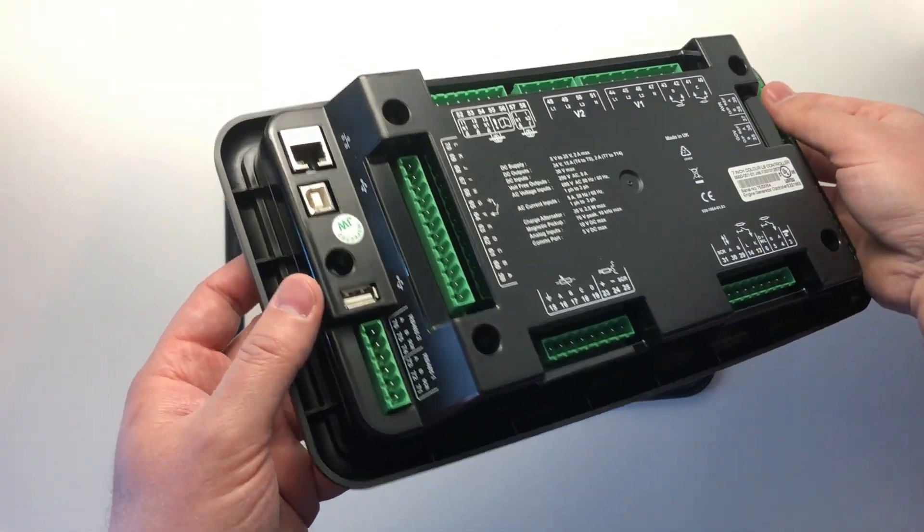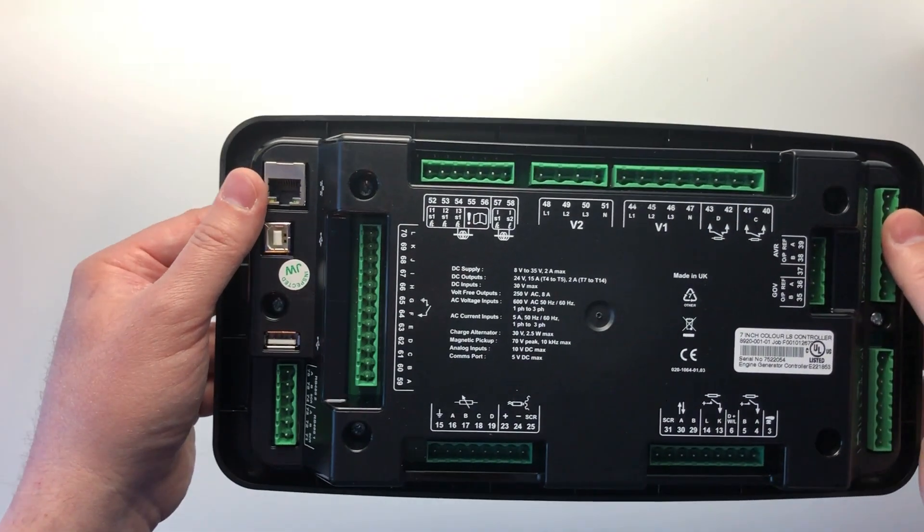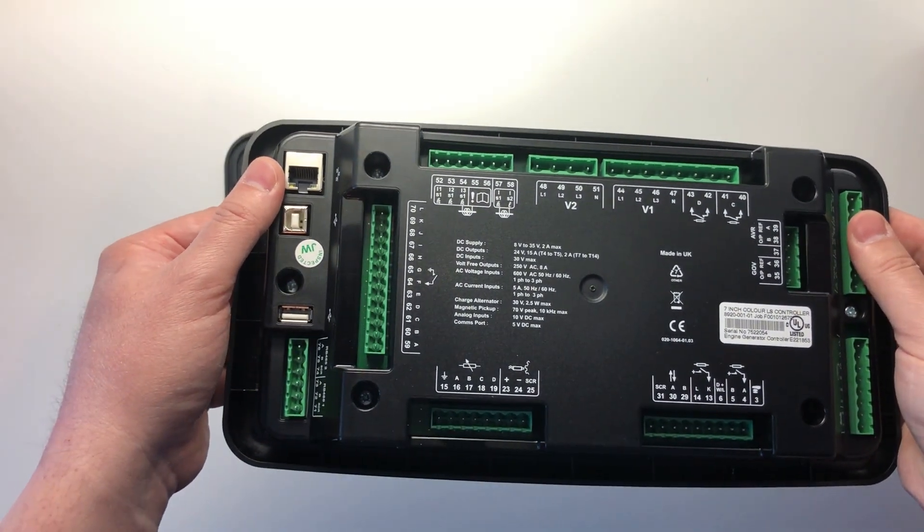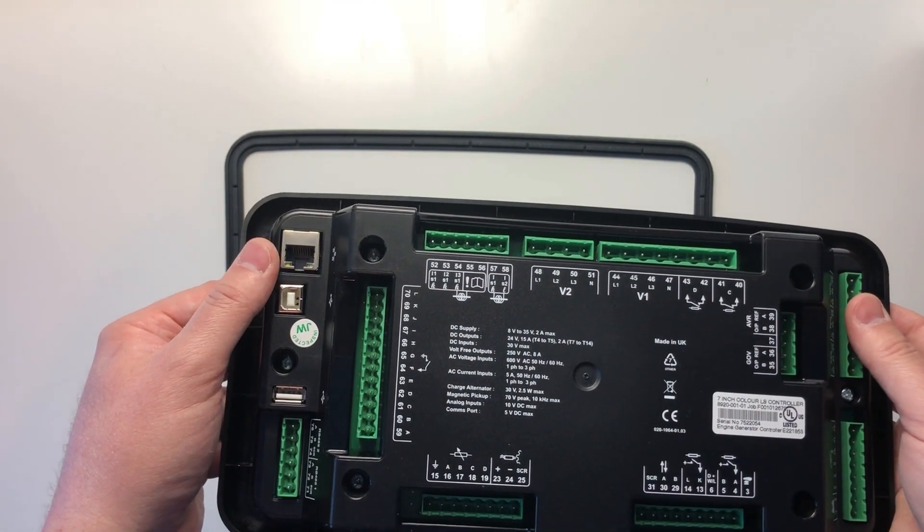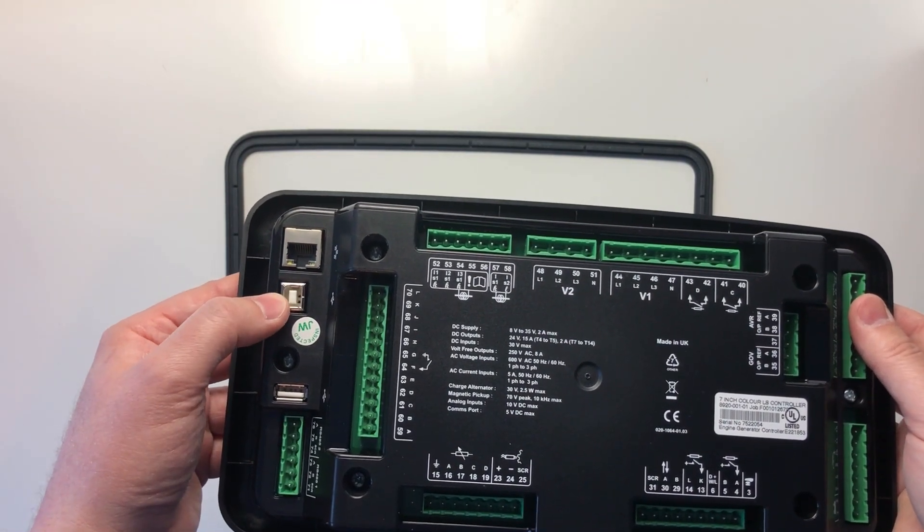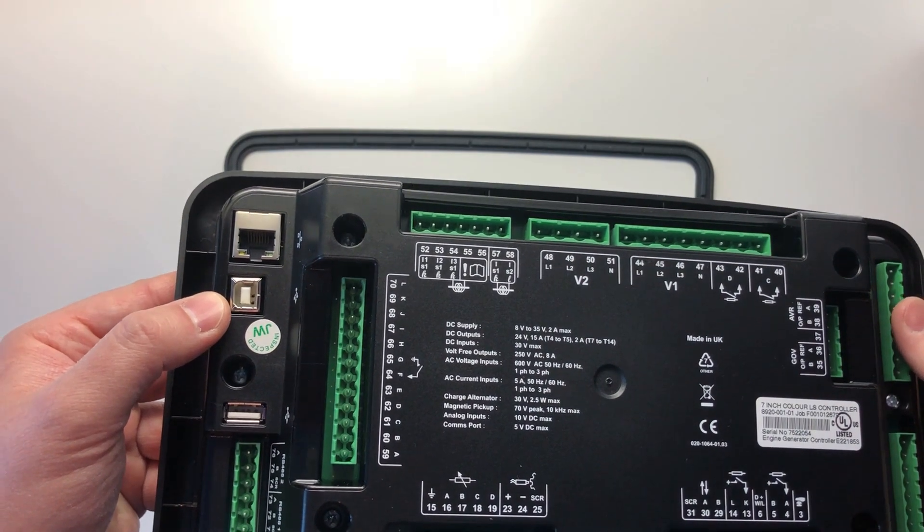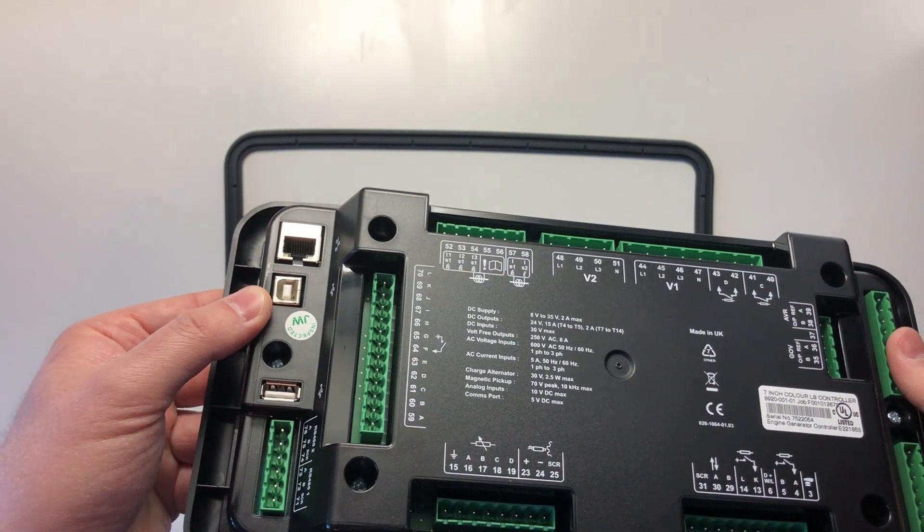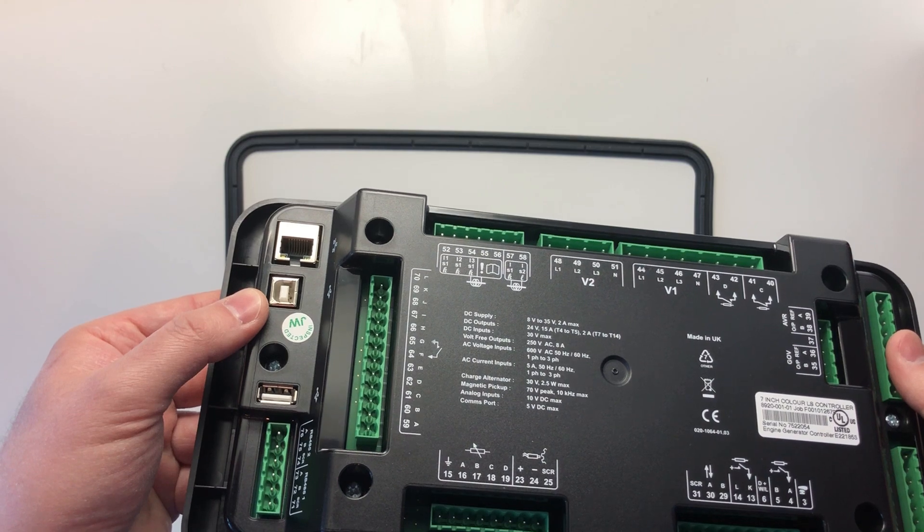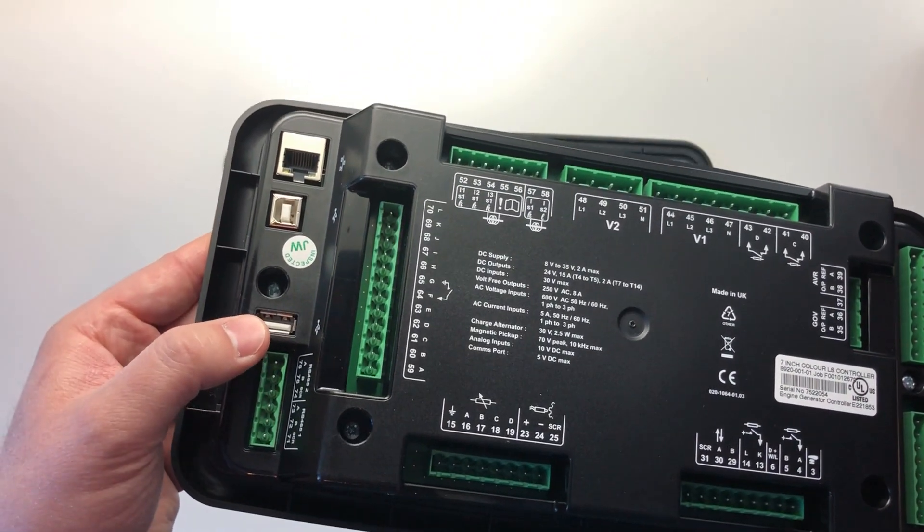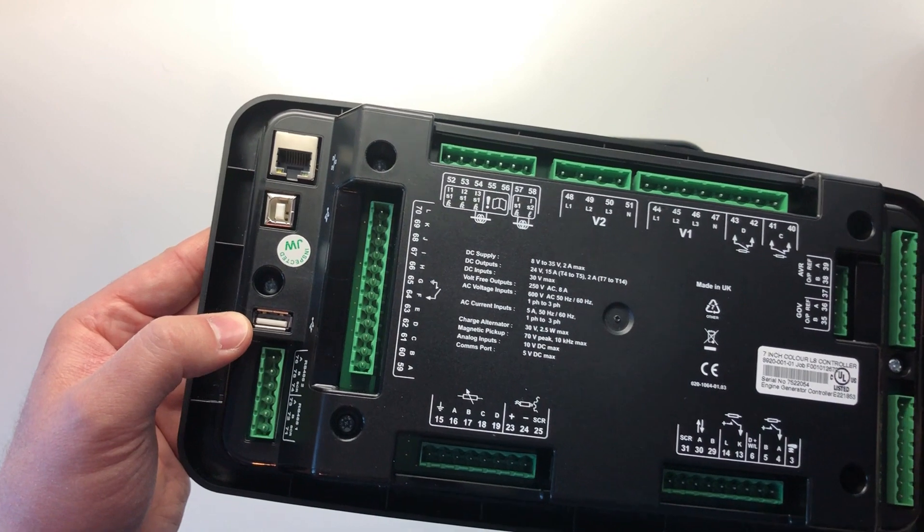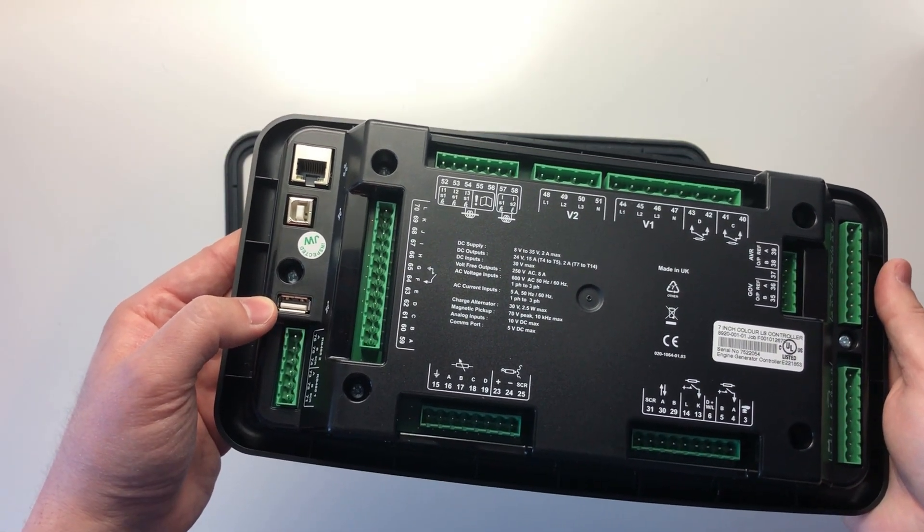On the left-hand side, we have the Ethernet port for Modbus TCP communications to connect to SCADA, PMS, or a remote monitoring system such as the DSE WebNet. We also have the USB port for connecting to a PC and configuring the unit using the DSE configuration suite software. There is also a USB host port which can be used for data logging onto an external USB drive.